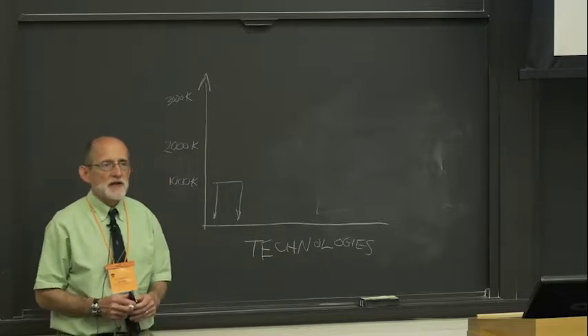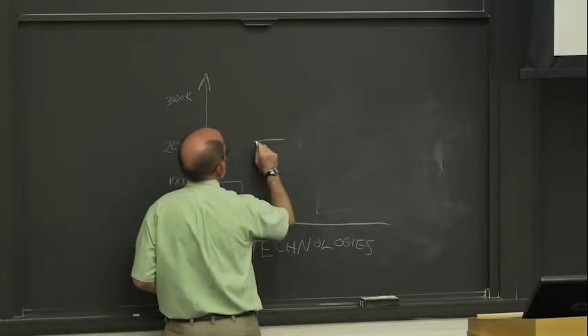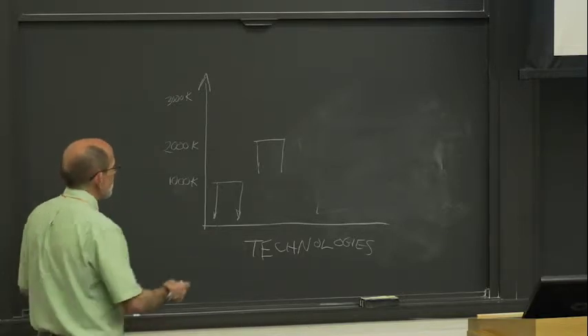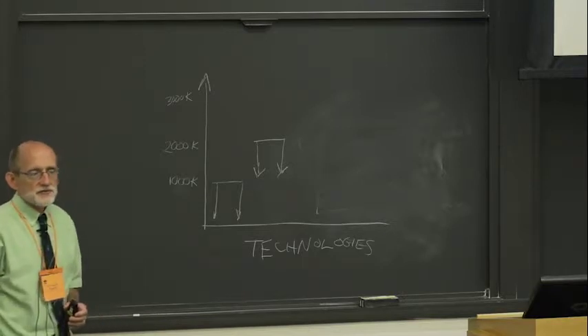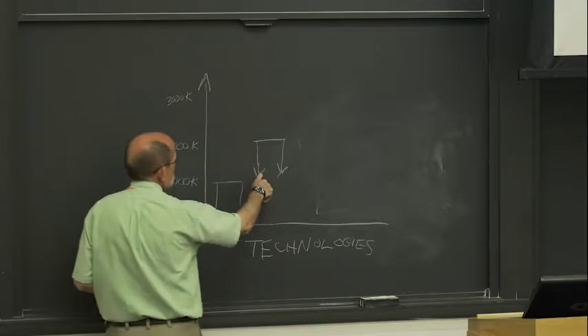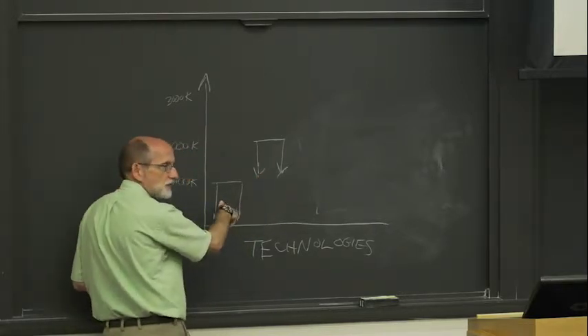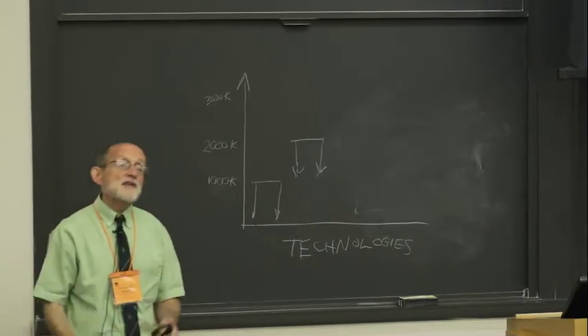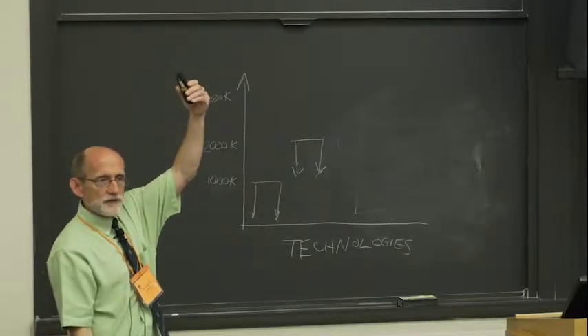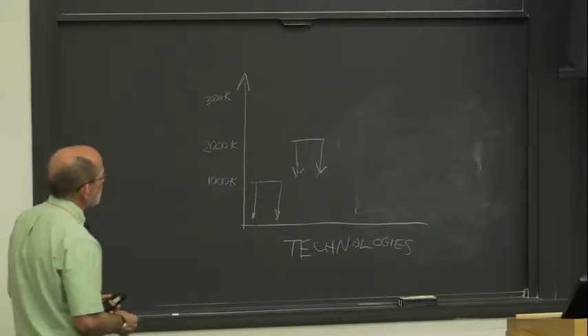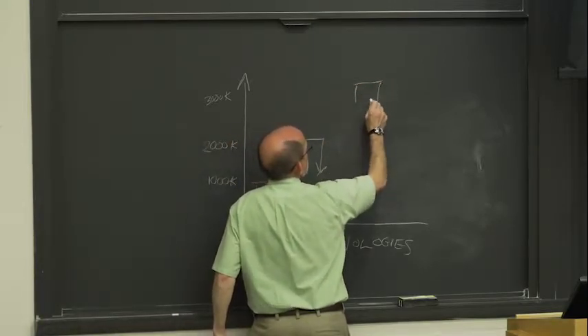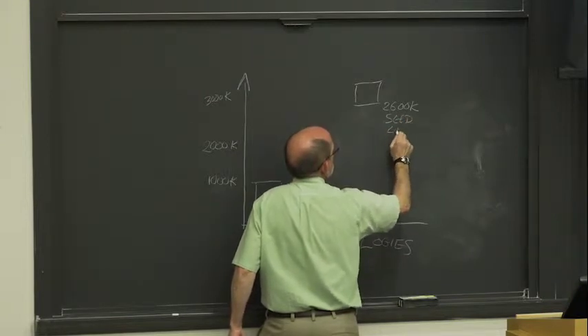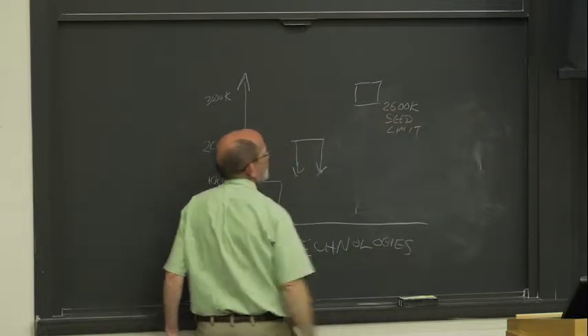People then realized: take the heat coming out of the gas turbine at 1,000 Kelvin and feed it into a steam cycle below — creating a combined cycle that spans from high temperature all the way down to ambient. That's why combined cycles are so efficient: a big temperature drop for the heat engine. MHD operates up at about 3,000 Kelvin, but you can't extract power below maybe around 2,600 Kelvin because the conductivity drops as the seed loses conductivity.